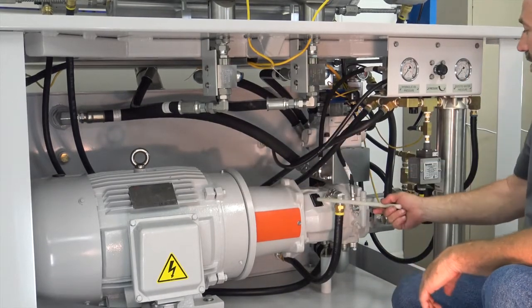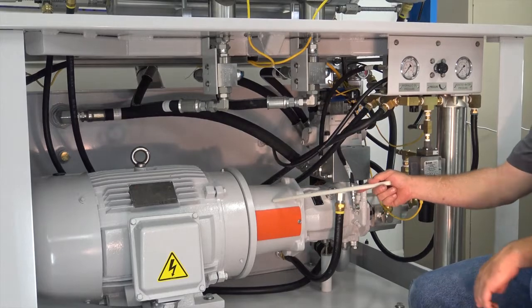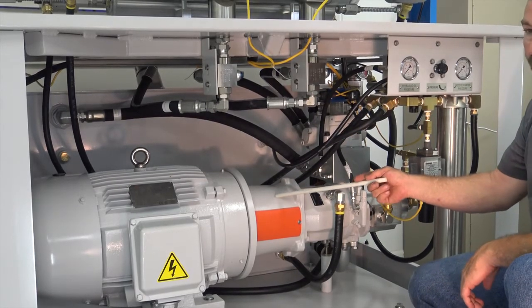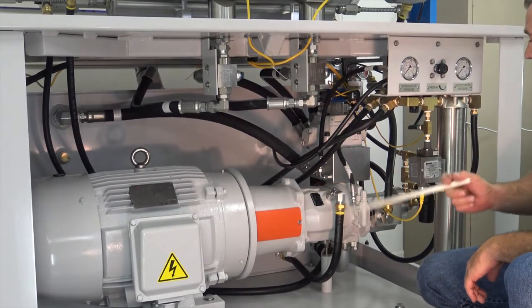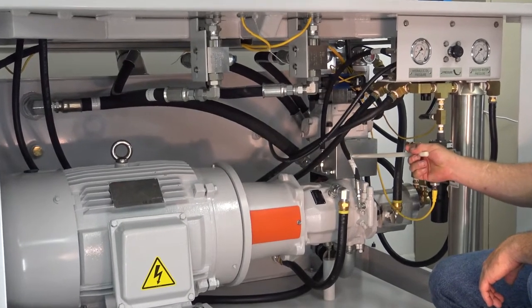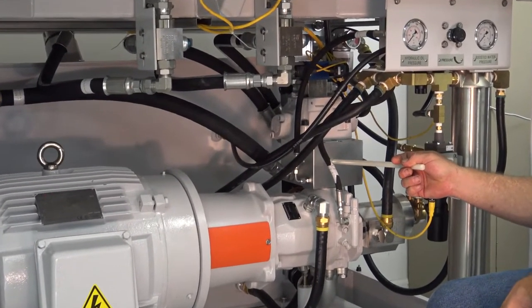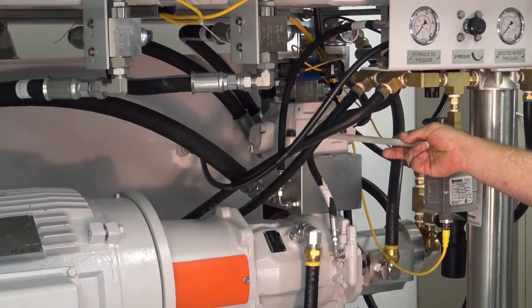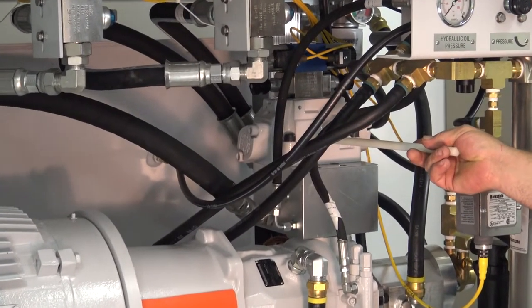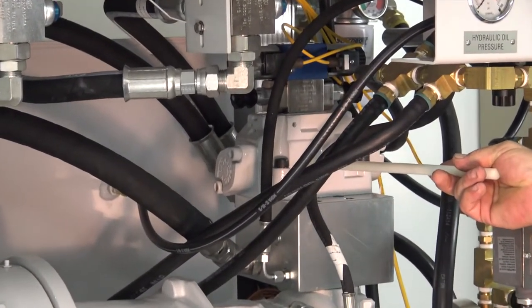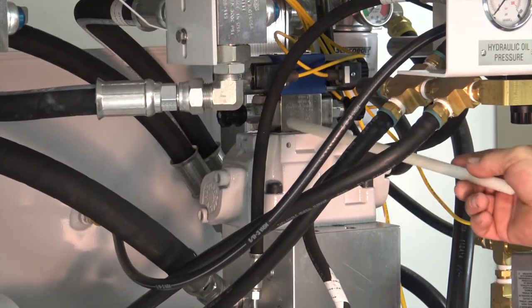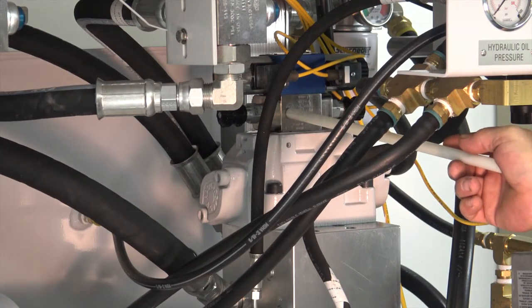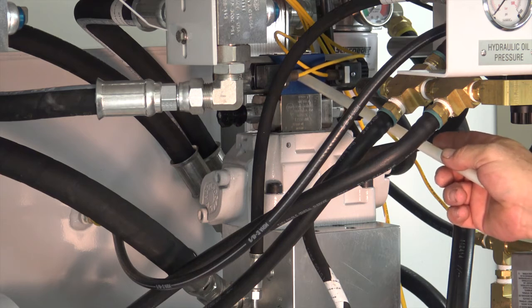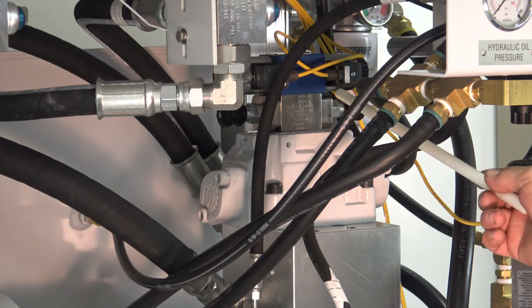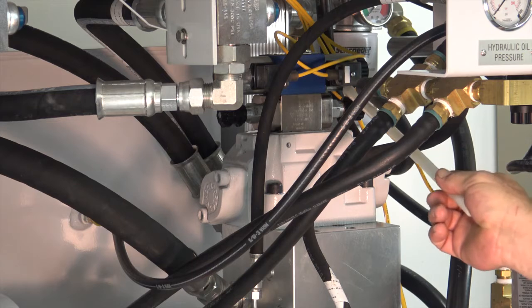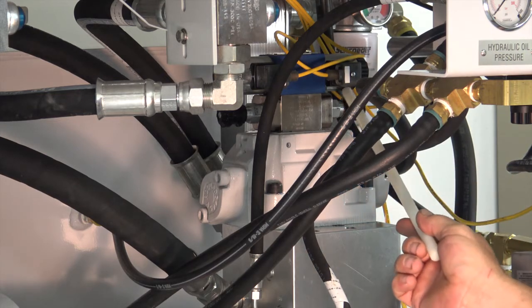Between your electric motor and your Rexroth hydraulic pump, you've got what's commonly known as a C-face adapter or the pump motor adapter. Above your Rexroth pump you have a directional control valve manifold. Above it we have the four-way valve assembly, or commonly known as a directional control valve. Above it we have a flow control, but on the top we have a pilot valve with an electric coil on either side. I don't know if you can see that, but the coil for it is up in there.